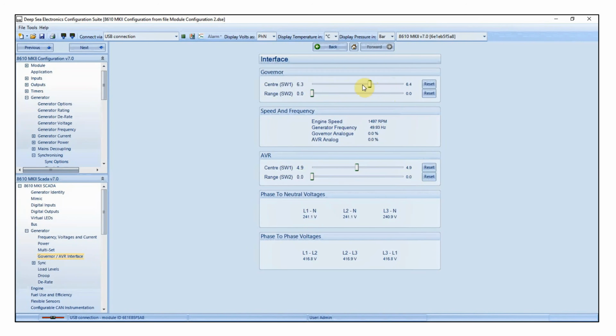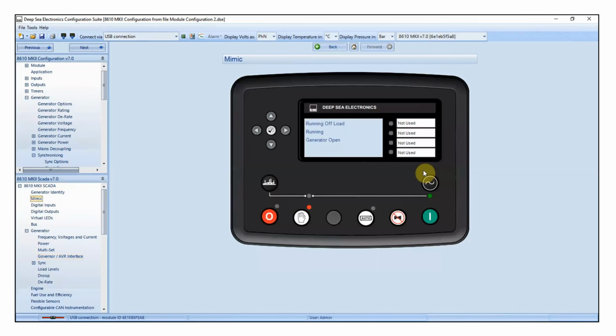So this time you'll see, as I close the generator breaker, rather than the frequency decreasing, the frequency has now started to increase, just as we expect. Now, we're expecting it to get to 52.5 Hertz, but you'll see it's stuck at 51 Hertz. This is because the switch 2 value is too small. All we need to do now is keep increasing switch 2 until we get to 52.5 Hertz with a governor analog percentage of 80%.